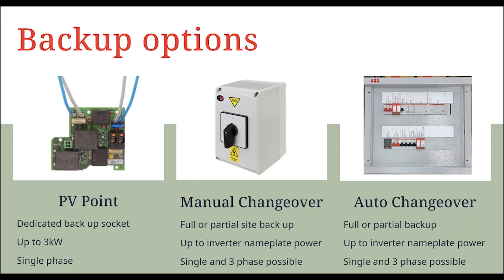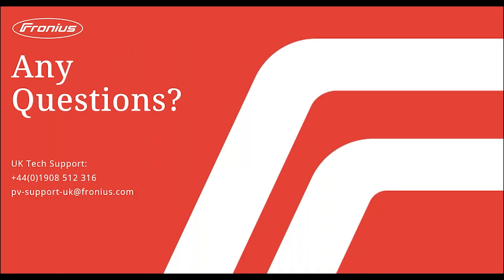What is the maximum off-grid power if they cannot be paralleled? So that will be limited to the battery-enabled inverter's power class. So I would recommend, if you want lots of power, go for a 10 kilowatt Gen24, either single or three-phase, and then you'll be limited to 10 kilowatts of power, assuming you've got maximum power from your battery and you've also got some solar energy coming in. It really depends on the size of the battery.